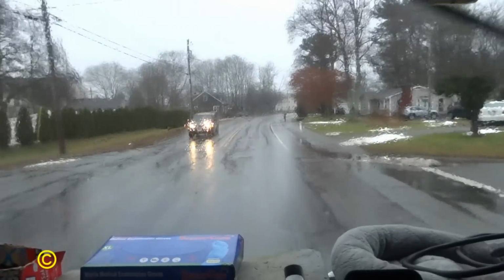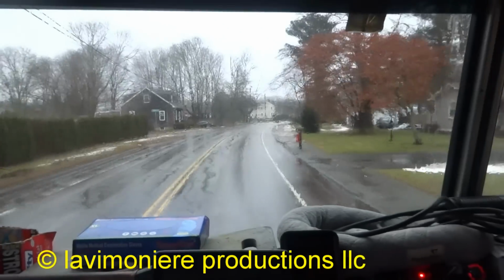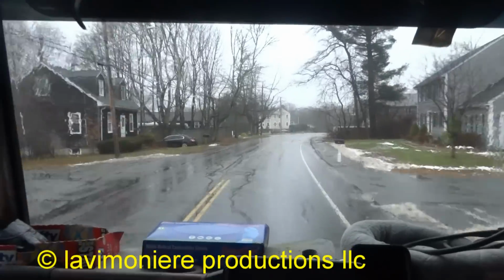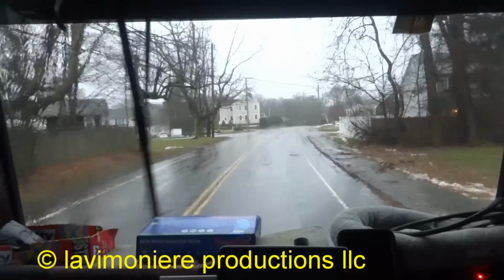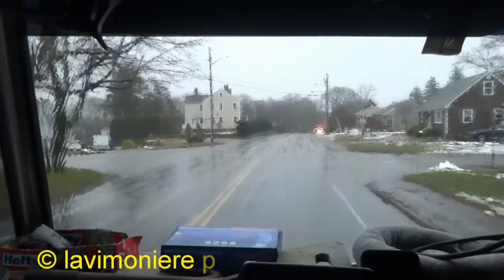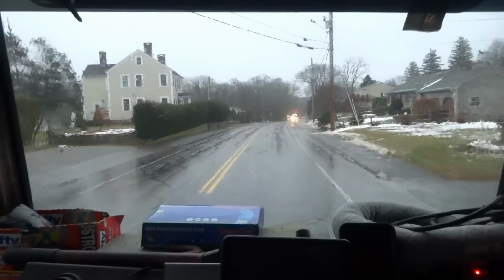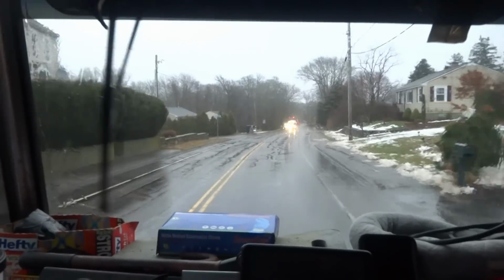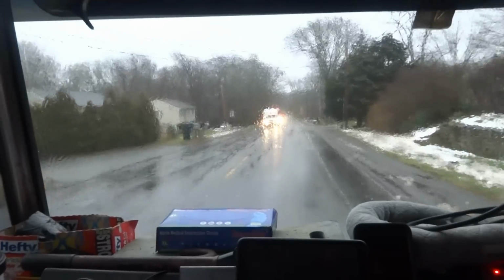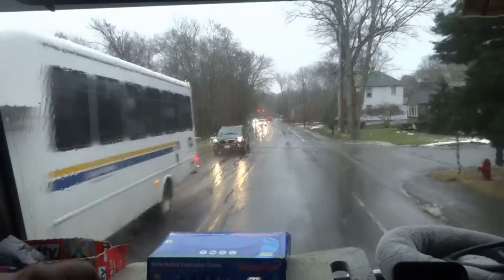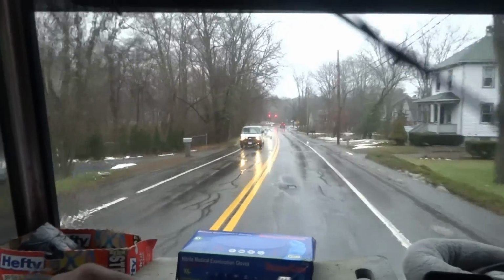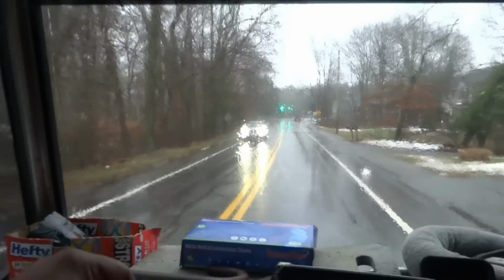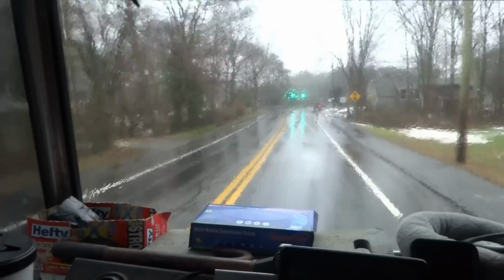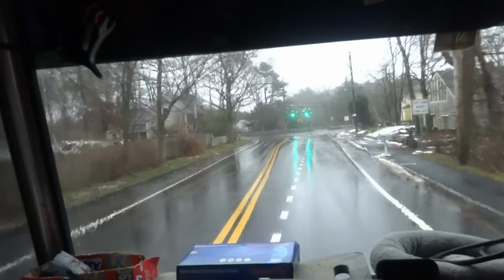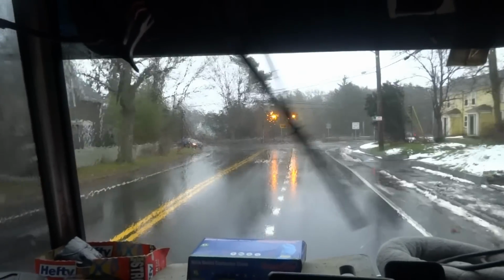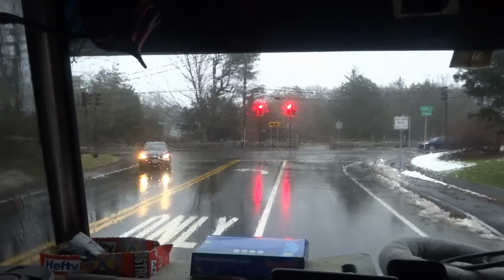Morning guys, December 9th, 2019. I got a call for no heat in an area that's more summer homes. Over the weekend a low temperature alarm went off, though it hasn't been that cold. I told the guy to go by in the morning, and he says it's going off on the low water limit control. It's an oil fired boiler that I replaced a couple years ago.